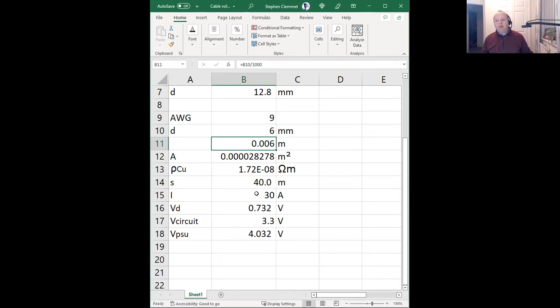And I think one of the key things to remember here when you're looking at cables is the cable diameter is always given in millimeters. So don't forget, if you do this calculation, to convert it to meters - just divide by 1,000 before you do the rest of the calculation - because the material's resistivity is given in meters, and you're given your distance in meters, so you don't want to suddenly have one unit in millimeters, because everything will go terribly, terribly wrong.